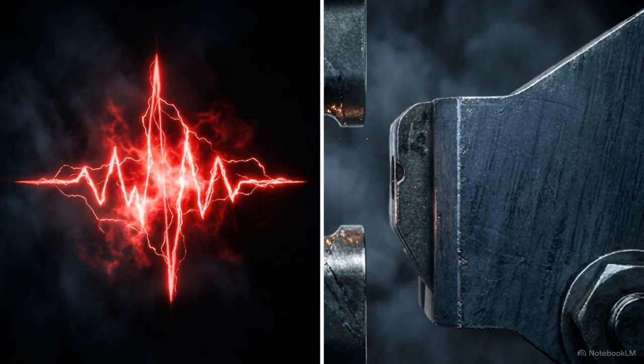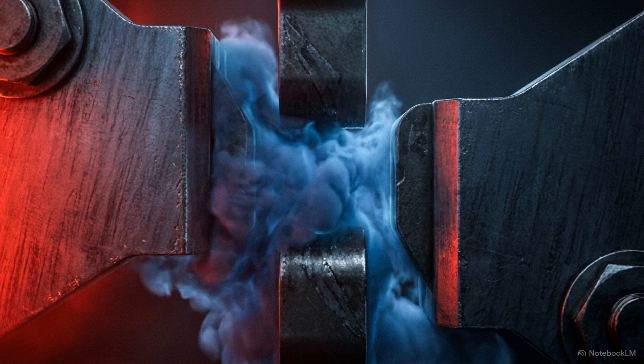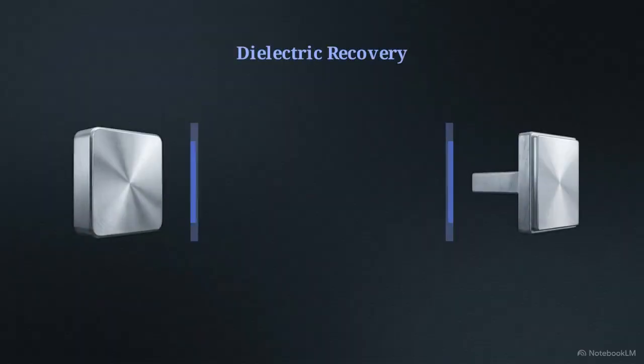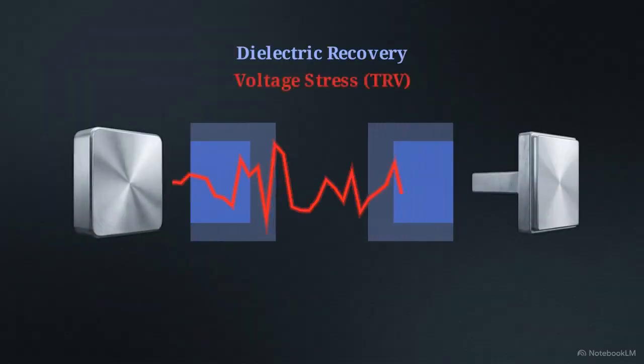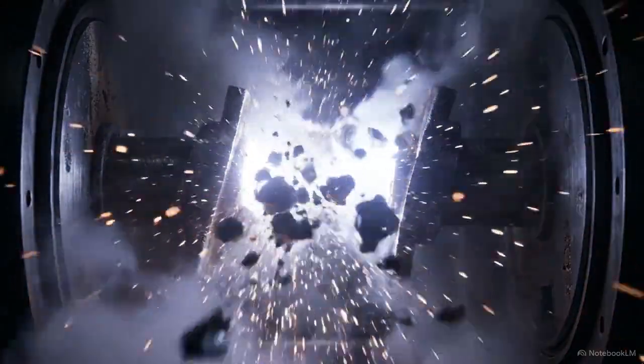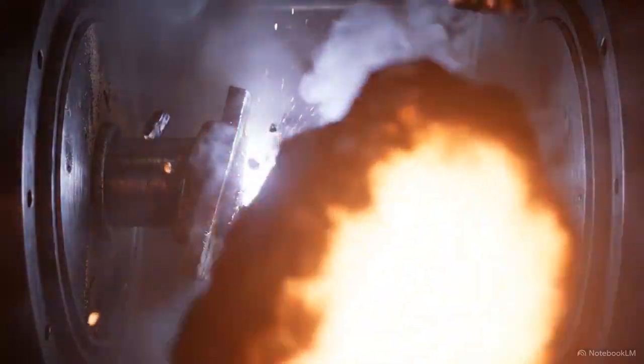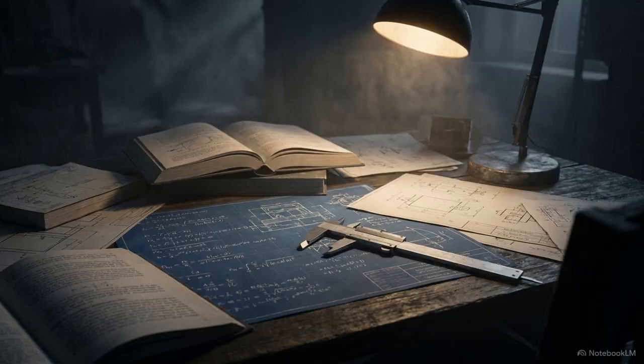What follows is a microsecond race between two opposing forces. On one side, the grid is applying a rapidly rising voltage stress. On the other, the breaker is frantically trying to rebuild the insulating strength of the gap between its open contacts. If the rising voltage outpaces the breaker's recovery, the gap breaks down. The plasma arc violently reignites in a restrike, leading to a complete interruption failure and potentially destroying the equipment. To understand who wins this race, we have to look at the math.